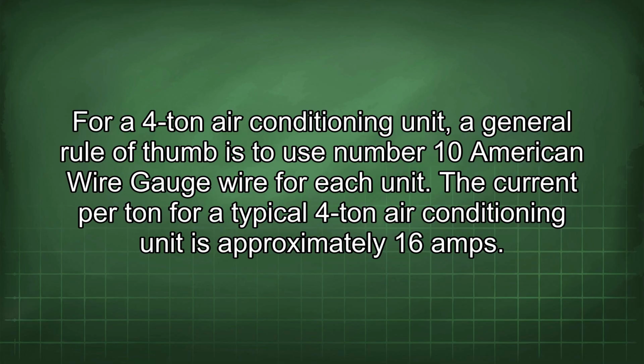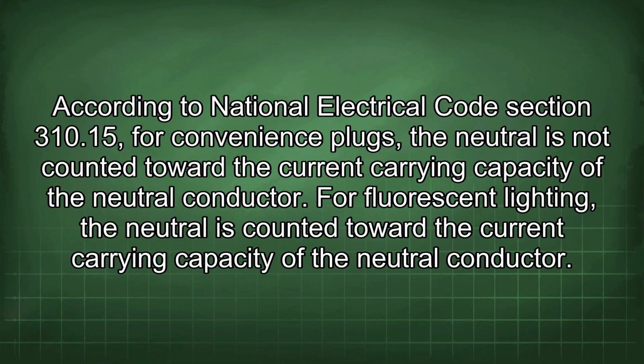For a 4-ton air conditioning unit, a general rule of thumb is to use number 10 American wire gauge wire for each unit. The current per ton for a typical 4-ton air conditioning unit is approximately 16 amps. According to National Electrical Code Section 310.15, for convenience plugs, the neutral is not counted toward the current carrying capacity of the neutral conductor. For fluorescent lighting, the neutral is counted toward the current carrying capacity of the neutral conductor.